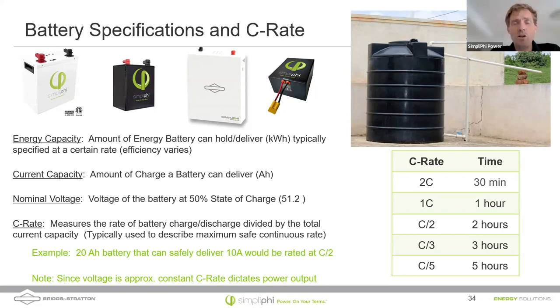And I do want to point out that the amount of energy that a battery can deliver depends on the conditions. So at slightly warmer temperatures, 30 to 40 degrees operational temperature of the cells of the battery, you get the most performance. And once you get above 25 Celsius, there's not much difference. But at lower temperatures, the electrolyte is more viscous. The other thing to point out here is that the output of a battery, the total capacity of the battery, depends on how quickly you discharge it. Right, so if you try to discharge very quickly, you don't get quite as much energy out of the battery. You generate a bit more heat. That Ohm's law of the I squared R, it depends on the square of the current.